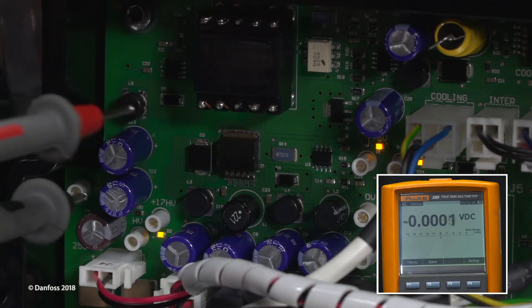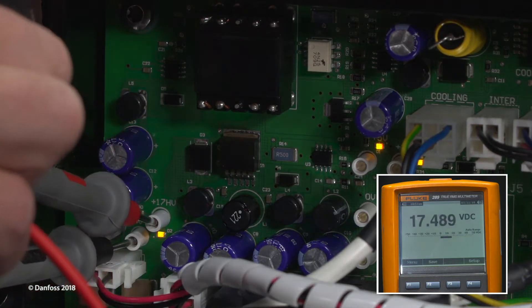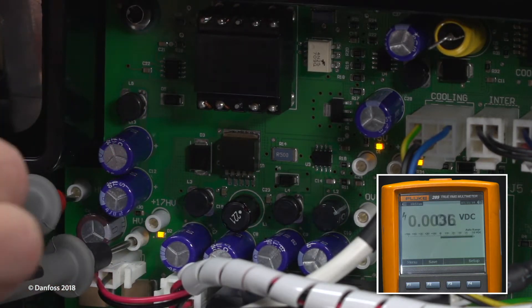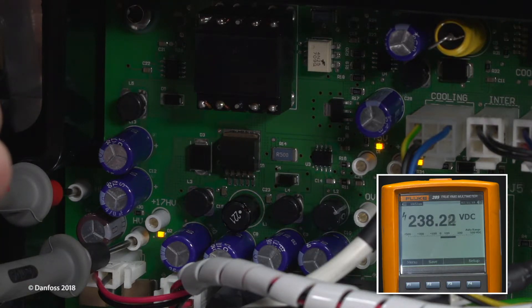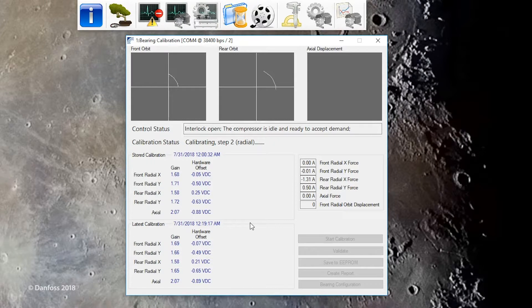If the voltage values remain the same, the PWM might not be the source of energy drain. Disconnect power to the compressor and reinstall the PWM. If the issue with the bearing system is not identified, the PWM may not be the source of the problem and other bearing system verifications should be performed.